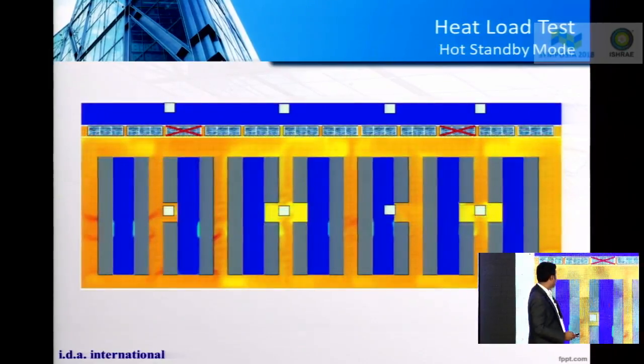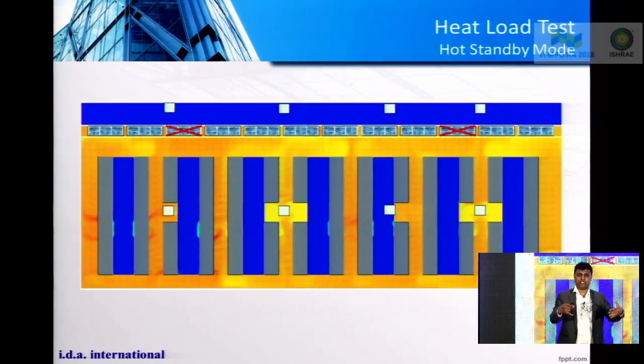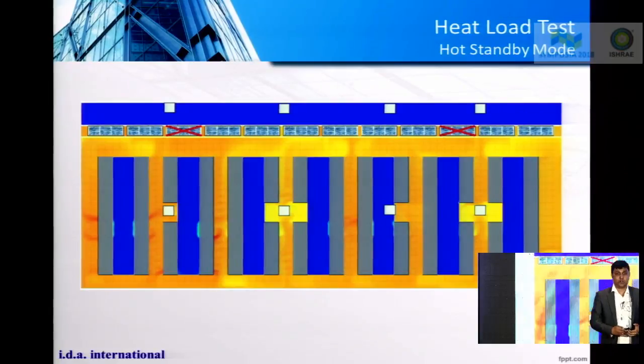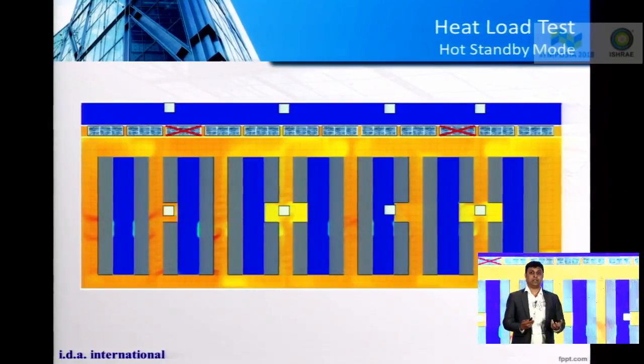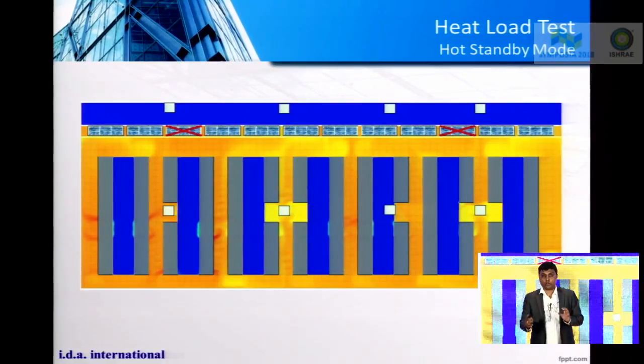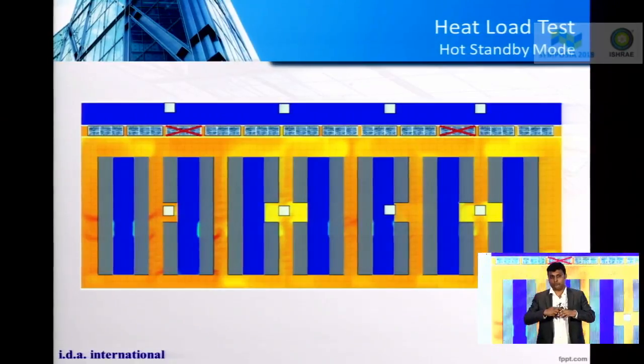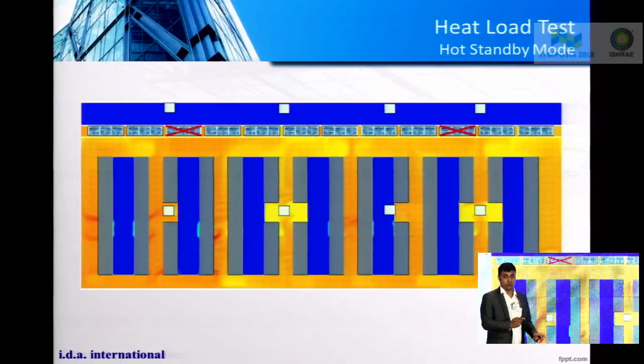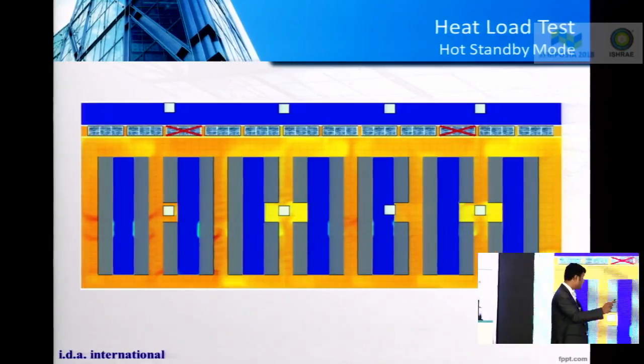I can switch off the extreme end CRAC units, or some of the CRAC units in the middle, or I can even switch off CRAC units that are next to each other, just to verify what could happen, or to verify the thermal conditions in different scenarios. So this is how you do a heat load test.